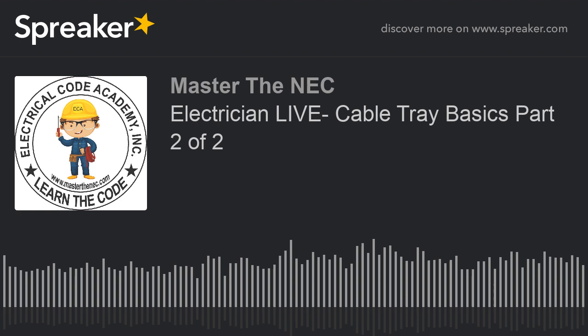So anyway, in that concept, what we did before is we need to come up with what the fill is for the cables and what the fill is for the single conductor cables. And as long as that sum, adding the two together, the percentages of fill doesn't exceed 100%, okay, then, based on the percentage values that you get, then we're okay. Then you can just treat each one independently, not overcomplicate it, and walk away. You know what I'm saying?